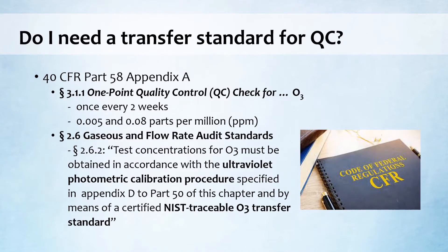When the 2020 Ozone TAD first came out, I initially thought that this would not apply to my air monitoring stations, but rather the standards lab where we get our transfer standard certified. This brought up the question: do I need a transfer standard for QC? If you look in the CFR, in Part 58, Appendix A, Section 3.1.1, that's where the requirements for one-point QC checks are defined. They don't explicitly state what equipment is required for QC checks, only at what frequency — at least every two weeks — and at what concentration, 5 to 80 ppb for ozone.